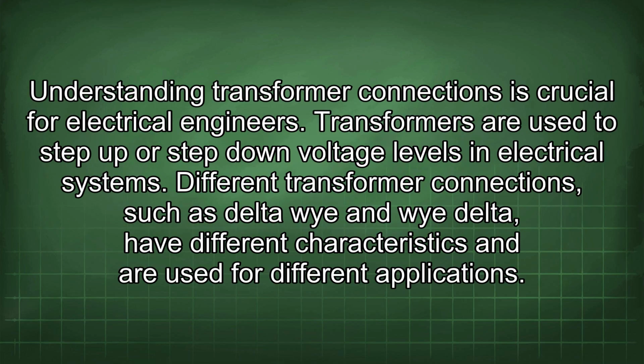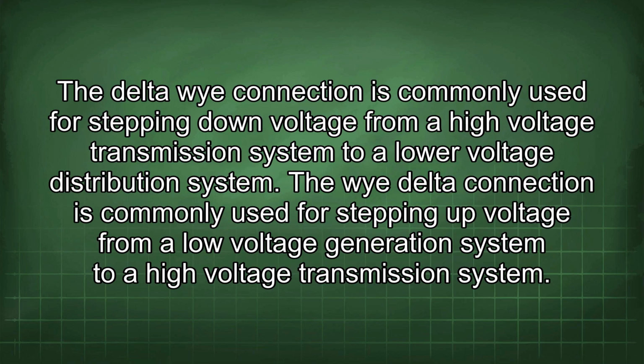Understanding transformer connections is crucial for electrical engineers. Transformers are used to step up or step down voltage levels in electrical systems. Different transformer connections, such as delta-Y and Y-delta, have different characteristics and are used for different applications. The delta-Y connection is commonly used for stepping down voltage from a high voltage transmission system to a low voltage distribution system. The Y-delta connection is commonly used for stepping up voltage from a low voltage generation system to a high voltage transmission system.